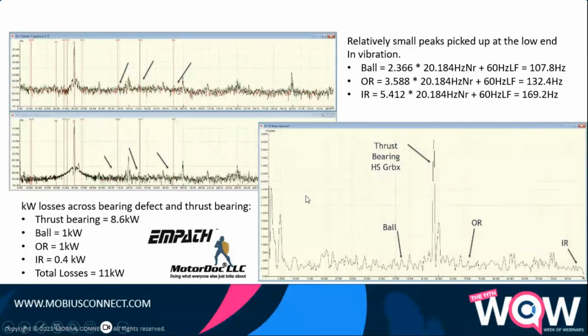So I said, hey, what did you do with the alignment? And as it turns out, the thrust bearing was so high because they had left out a shim. So the coupling was bolted together, and it was causing some damage on the thrust bearing. But we had the other losses as well, so a total of 11 kilowatts.